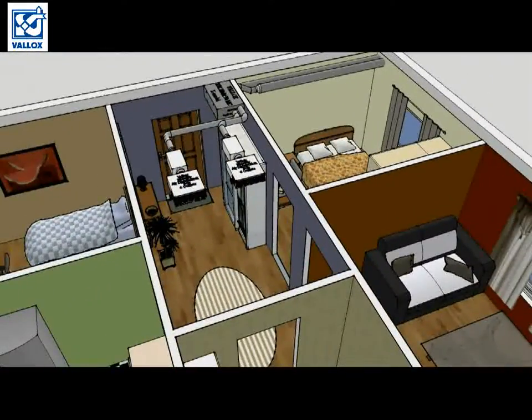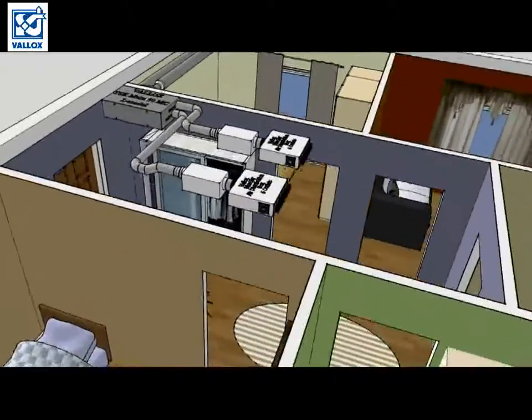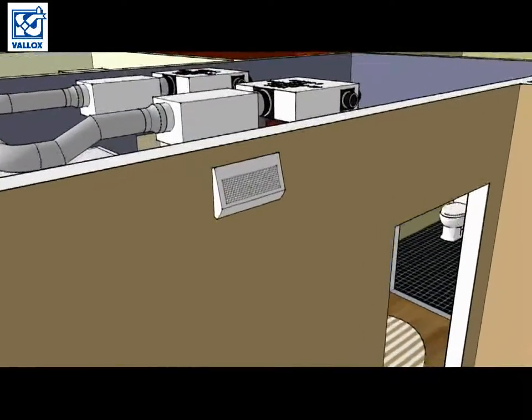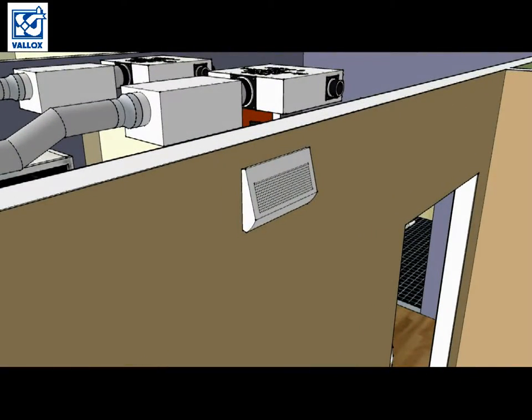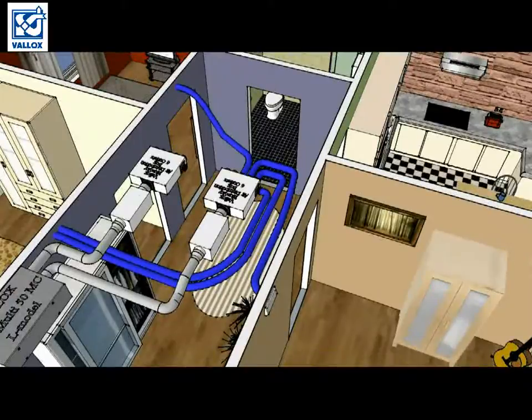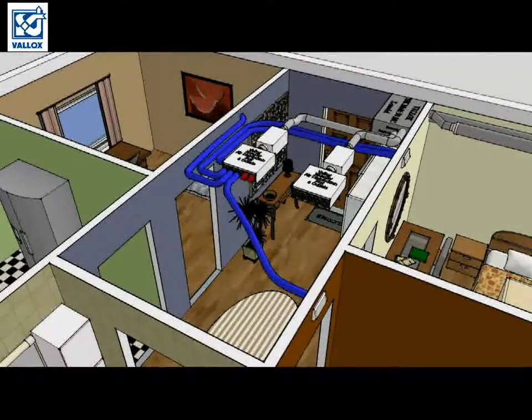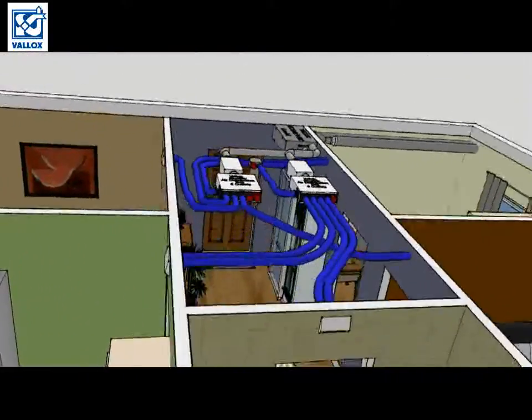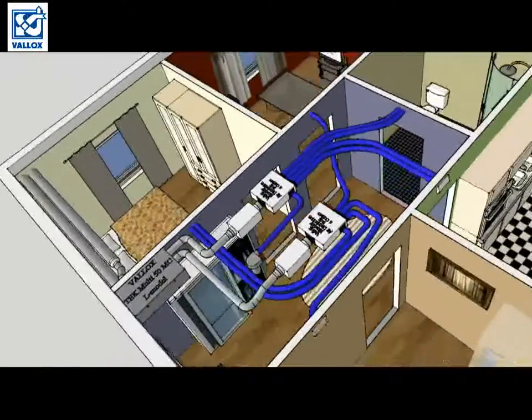Now back to the hall. We will bring supply air to bedrooms and to the living room. We will extract air from toilet, kitchen and hall. We will use supply air vents that have 75mm outlets, so they are fully compatible with Vallox BlueSky ducts. For the extract air vents, we will use the same principle, except for the hall, where we will use a BlueSky connection part for side connection. In this case, the main area for implementing the ventilation system was the hall.